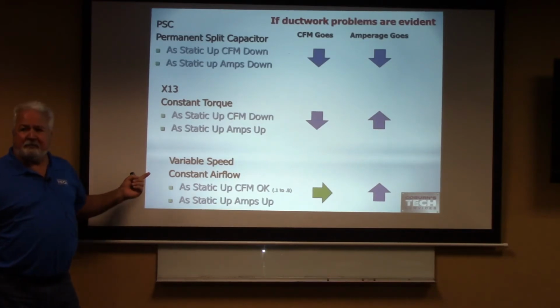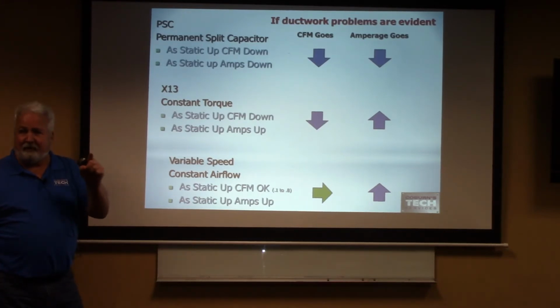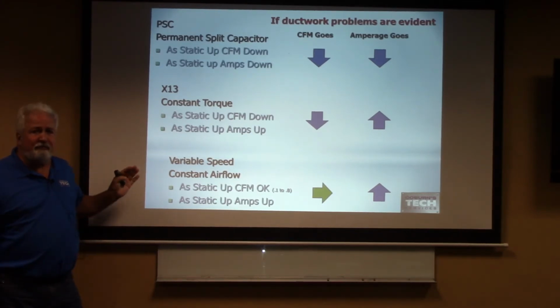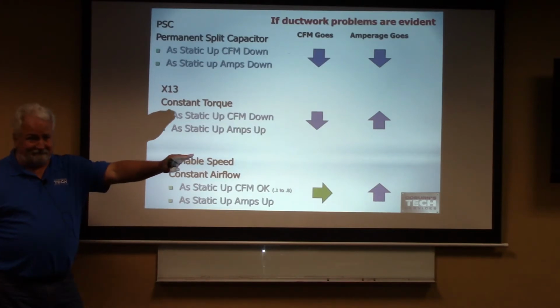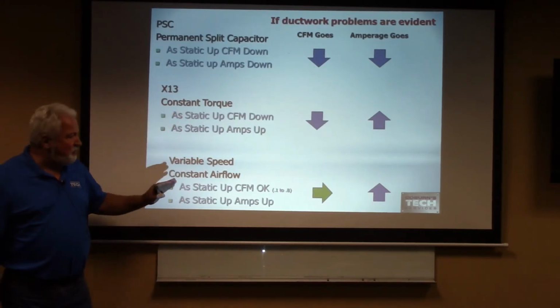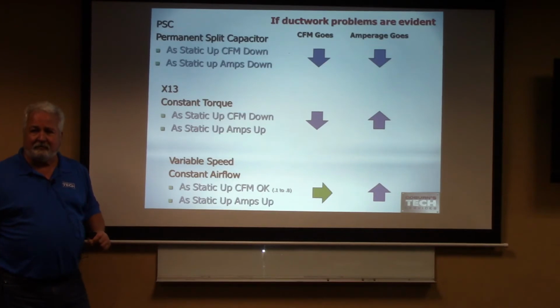All right? On a variable speed application, on a true variable speed motor, its job is to get that airflow out there. Whatever airflow you're asking for, its job is to get that airflow out there. So if I put that true variable speed motor on that bad duct system, what's going to happen to the airflow? It's going to get it, right? It's going to make that thing happen to a point. I mean, up to about 0.8, it's going to get it out there. What's going to happen to the amperage on that motor? It's going to get you that airflow or die trying. Does that make sense? So when you start playing with some of these variable speed motors, they may try and get you that airflow that you're looking for, but in both cases, they're going to kill that motor.